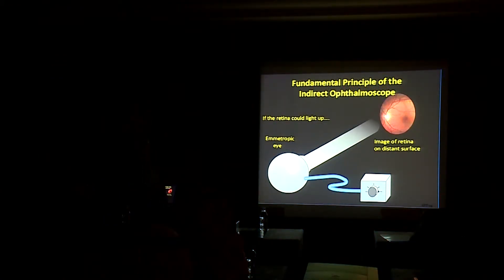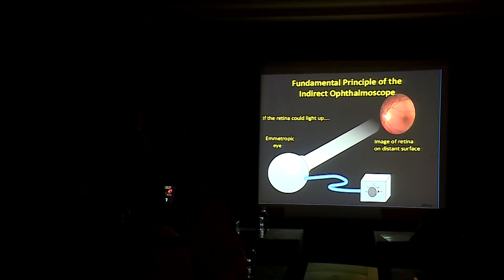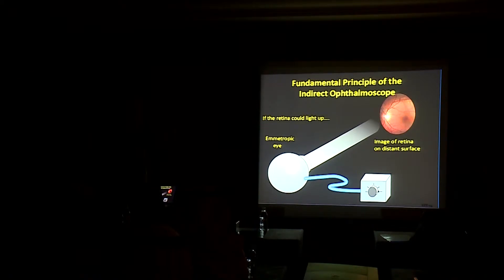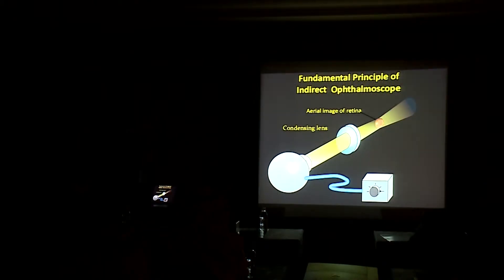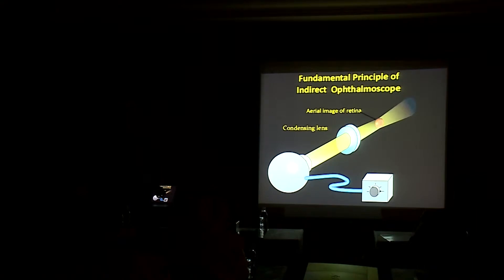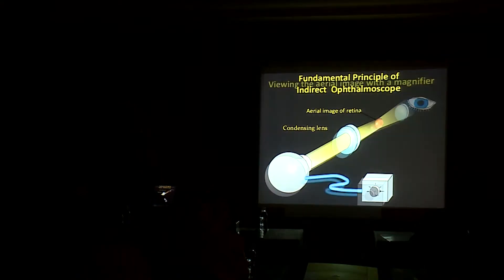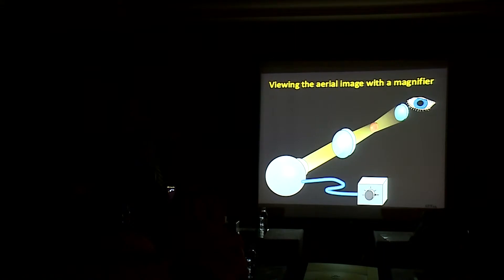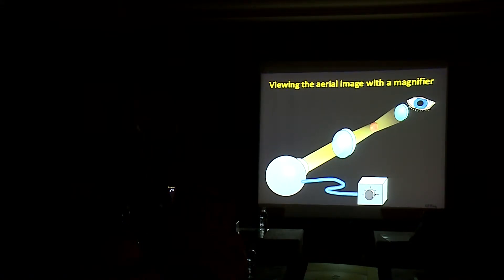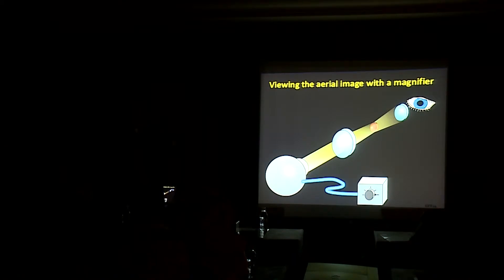The retina could be lit up by using the light source in the indirect and then interrupting this image coming out of the retina by a condensing lens. We get an inverted image of the retina, and we view the aerial image with the magnifier. The magnifier is the lens we are using to see this image.